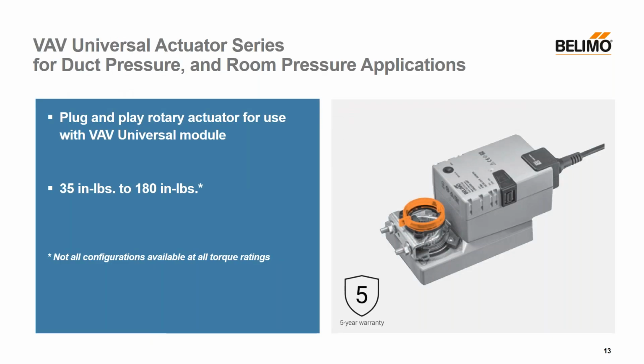Next, we have in the airflow measurement and control damper actuator sections that will begin on page 1-13. And for the VAV Universal Actuator series, you'll find this on page 1-16. These are VAV compact actuators for use with VAV Universal Sensor Communication Module that we'll show on the next slide. And these are available in non-fail-safe, mechanical fail-safe, and electronic fail-safe. The run times range from 2.4 to 120 seconds, and the torque ranges from 35 inch-pounds to 180.